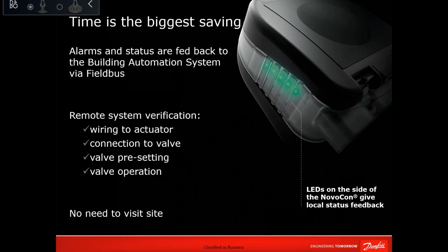Okay, next question: presetting is not required now as it's done by Novocon. Yes, you don't need to set the valve. You keep it at 100%, 120, whatever setting you keep. It can now be recognized by the Novocon, and you can change that setting. In case you have a doubt, when the Novocon is fixed on any valve, the first thing it will do is the auto calibration. When it does the auto calibration, it will show you the actual stroke length of that valve.